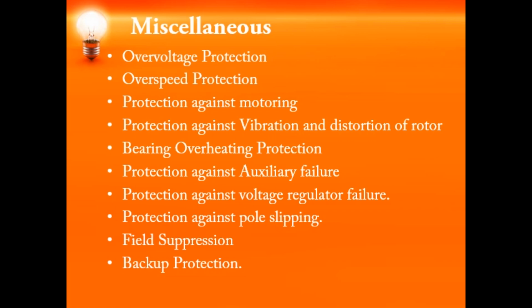In order to protect against overspeed, we need to have overspeed relays, wherein the setting of the overspeed relays, for example for the hydro sets, is around 140%.